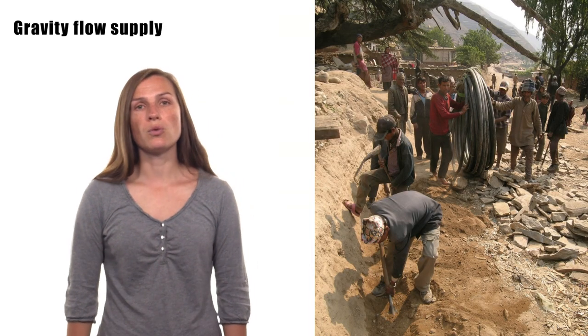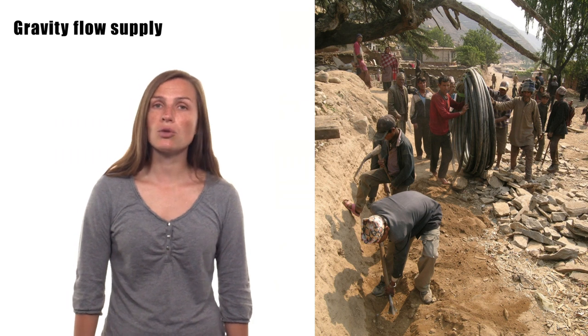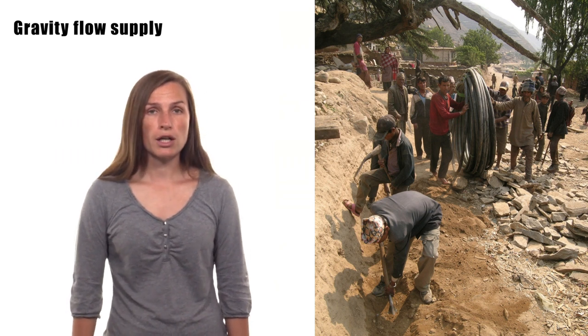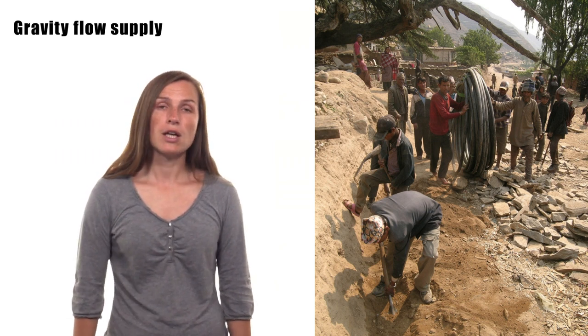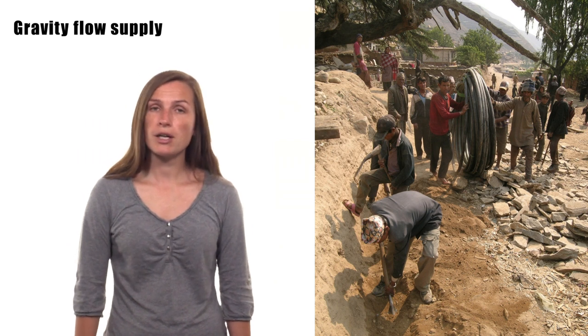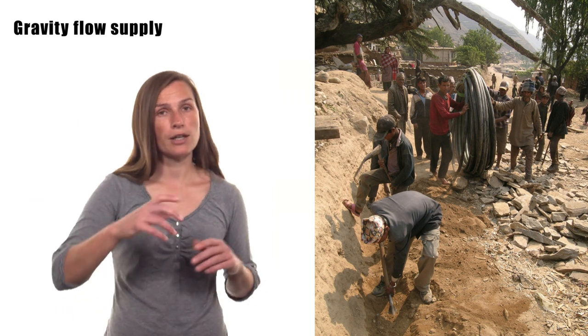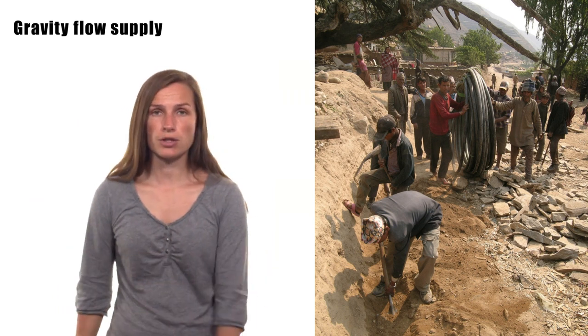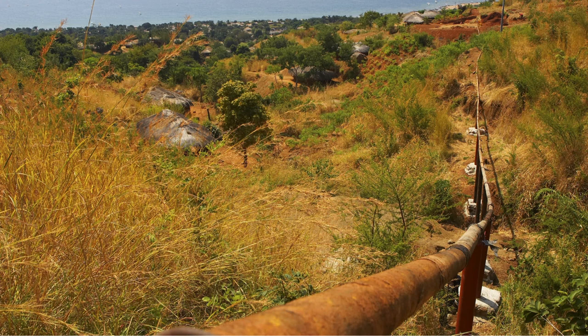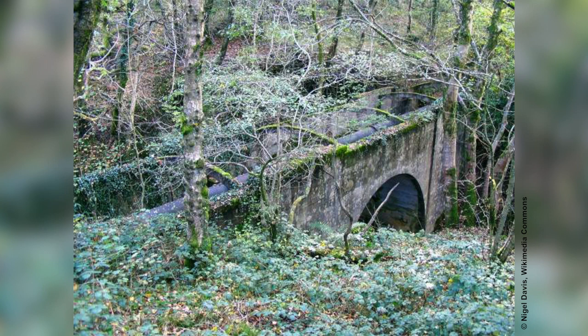To design a gravity flow water supply system, you would need to calculate the pipe diameter required, considering the elevation differences, the losses due to friction in the pipe, as well as energy losses produced by turbulence introduced by everything which is not straight, like valves, elbows or reductions. Furthermore, you would need to study the topography of the system to minimize high and low points which can lead to air trapping or accumulation of sediments, and to avoid negative pressures. Break-pressure tanks might be required if the height difference is considerable.